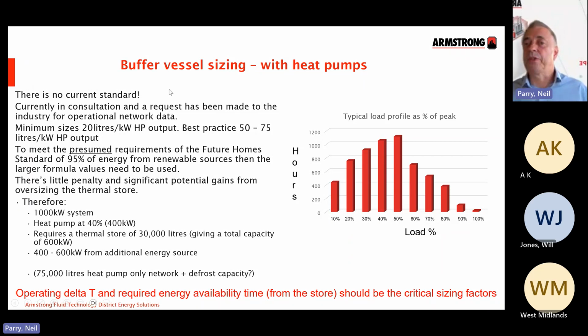So there isn't a current standard on how to size thermal stores with heat pumps, but there is lots of data out there, and the Ground Source Heat Pump Association make a comment that their minimum size would be 20 litres per kilowatt of heat pump output. I think that is absolute minimum in my view, and I think we need to be looking at a bit higher than that, maybe somewhere around the 50 to 75 litres per kilowatt of heat pump output, 50 being for maybe larger systems where you've got some inertia in that pipework as well, 75 litres per kilowatt on smaller systems where you've got less inertia in that system.